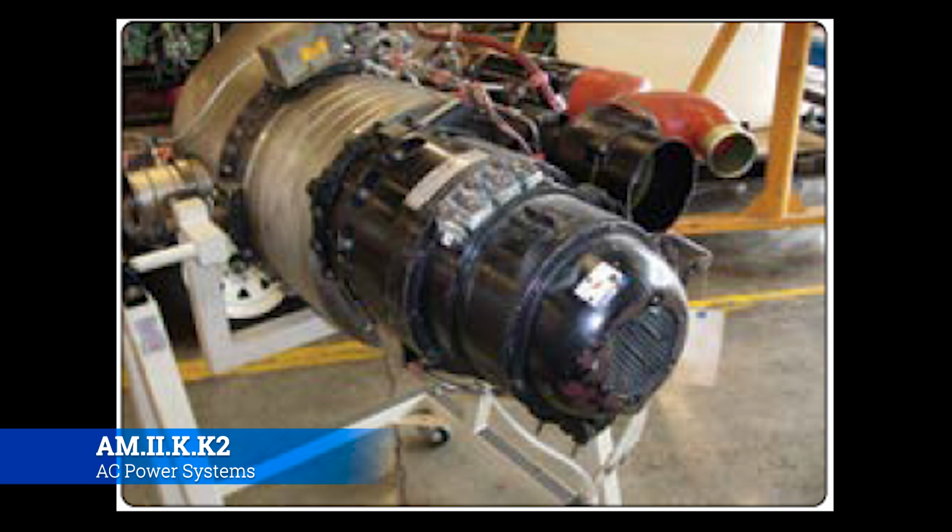Those magnetic pickups that grab the electricity are really useful, and they drastically improve the life of the alternator, simply because you don't have a consumable part in there. So that means there's less maintenance. That means there's less debris entering into the windings and all the bearings and everything that moves inside of that alternator. So it prolongs its life almost indefinitely.